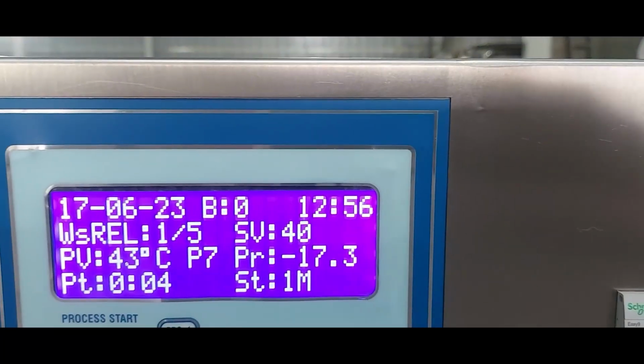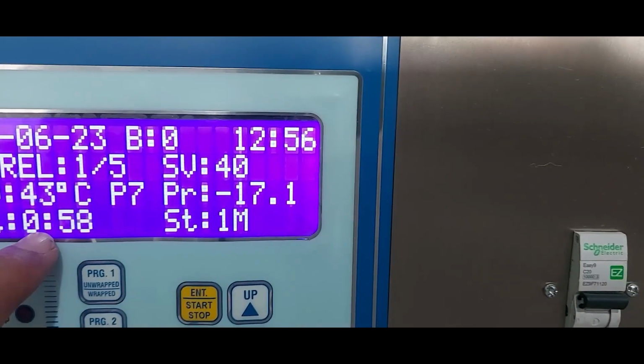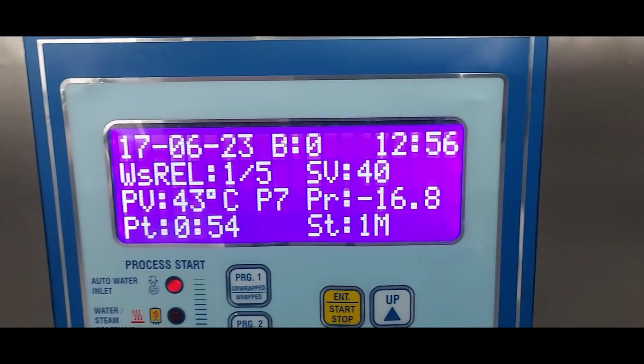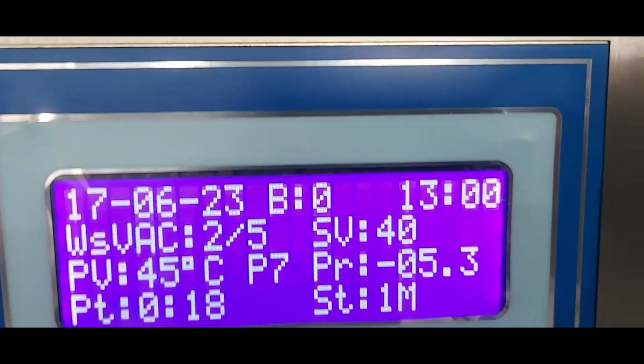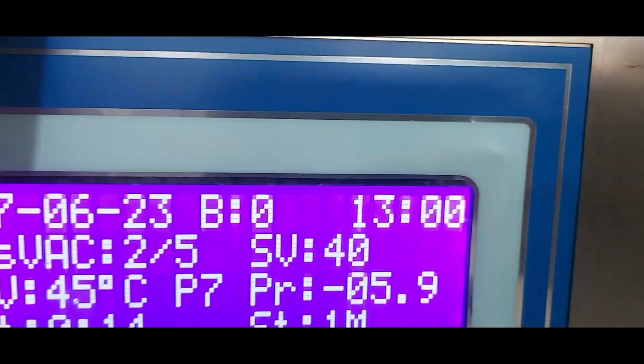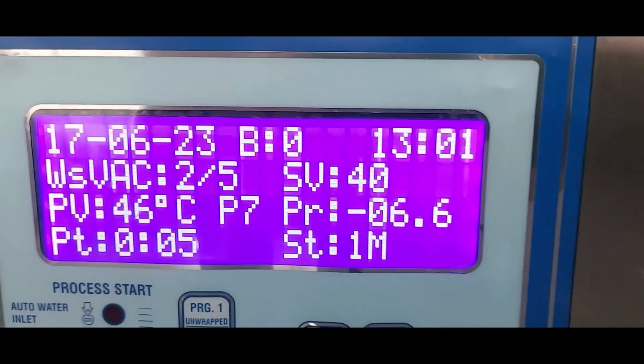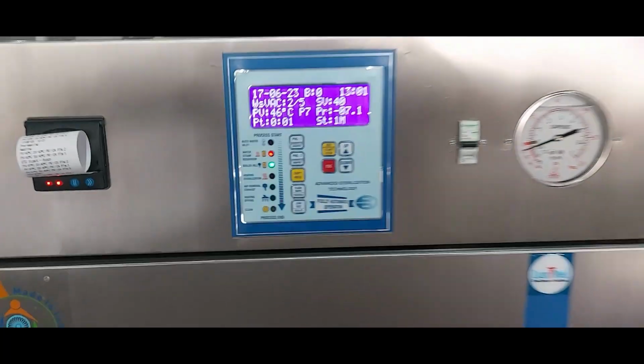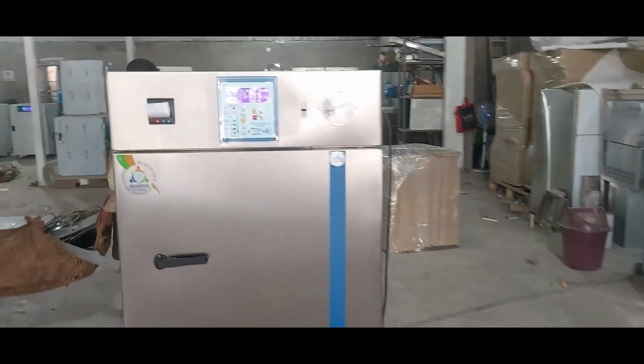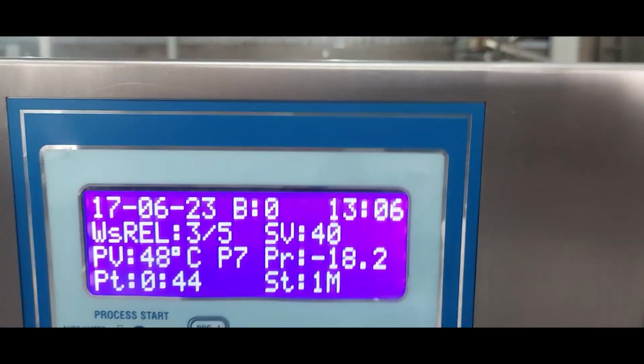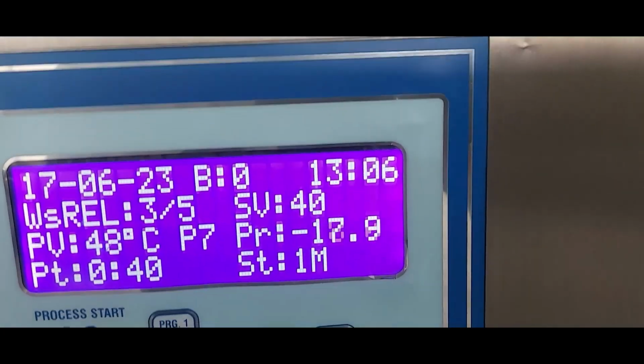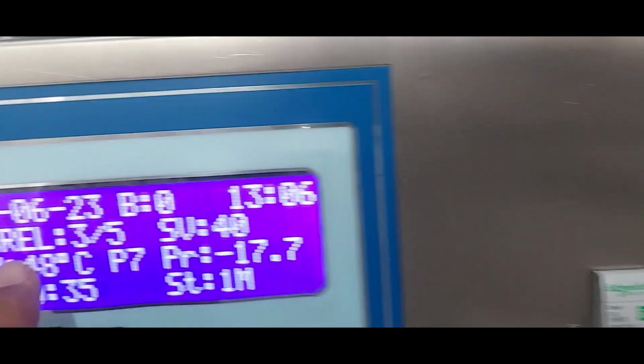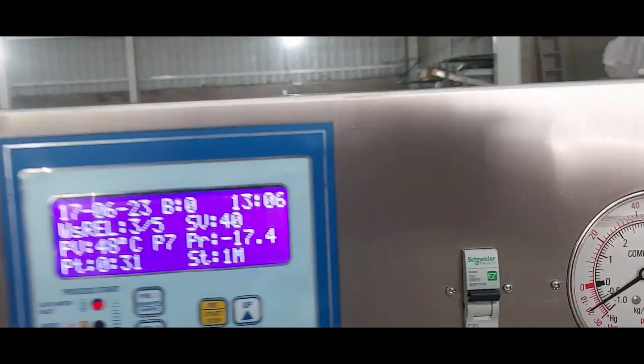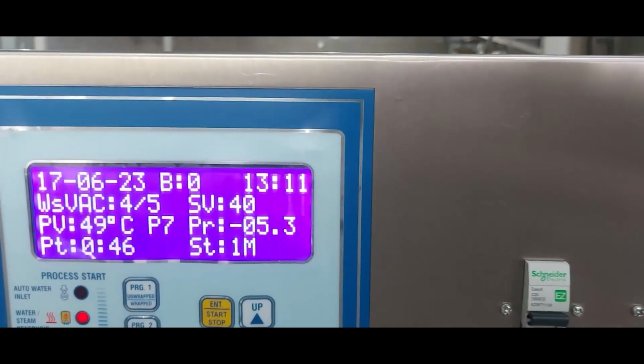This is the release cycle. After completion of this release cycle, pressure goes here. Once the pressure goes below 5, then the vacuum will start. The vacuum will go up to minus 20 here also. Then again the release cycle will start from here. So this cycle will continue up to the next level. This is the third cycle, and again the release is started. This is the third vacuum cycle in the machine. Once the pressure goes below -5, again the vacuum will start and release will stop.